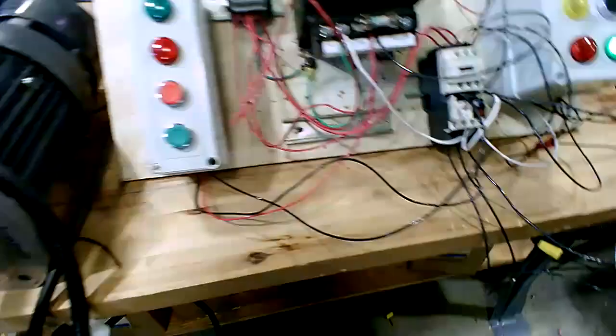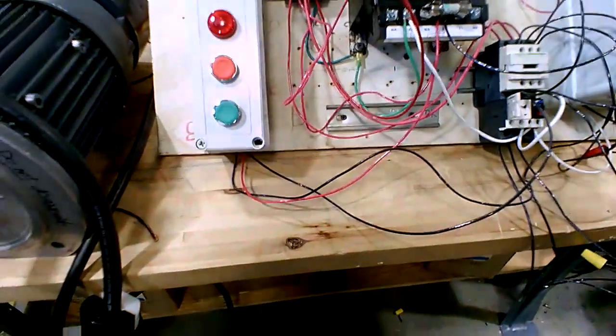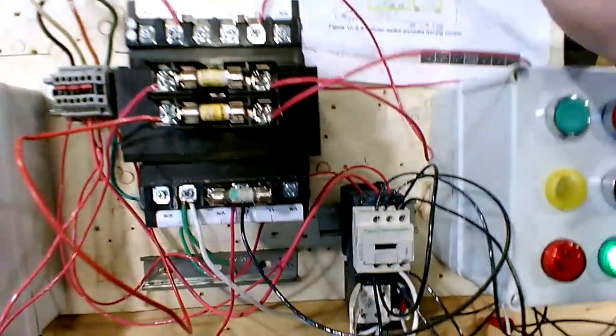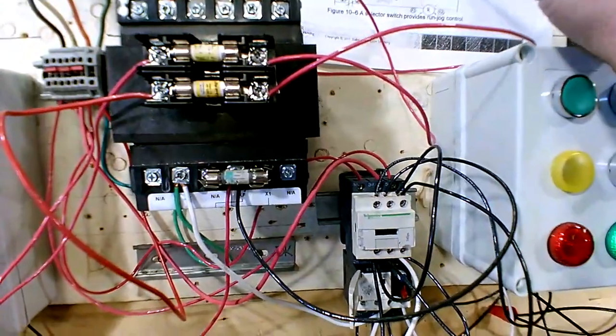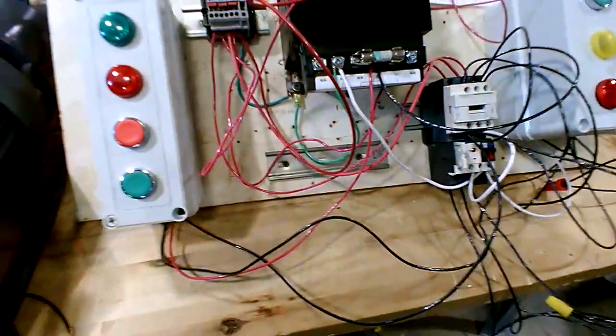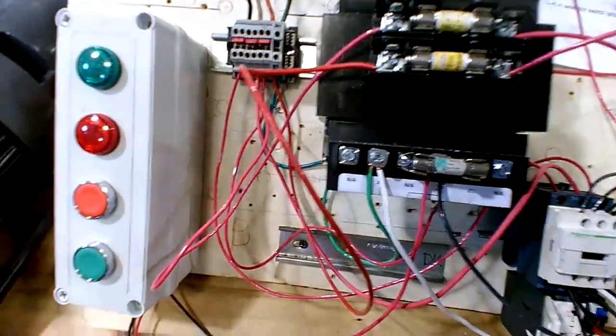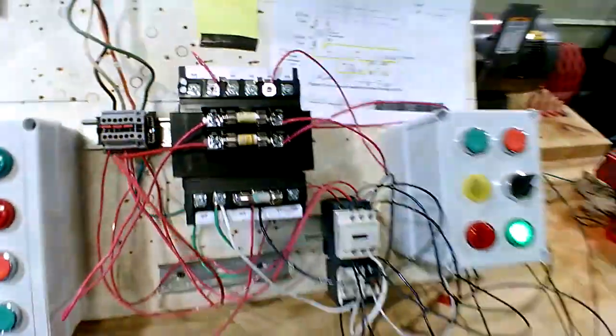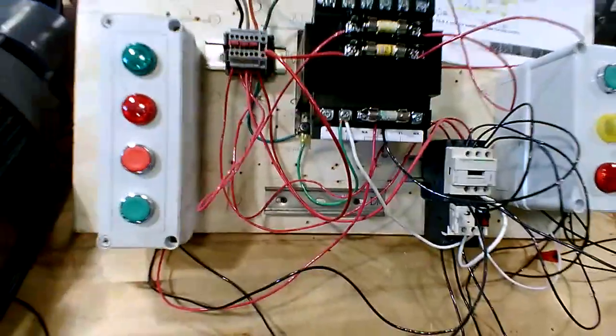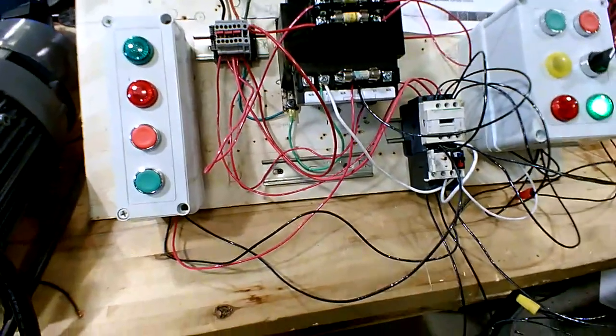So when the motor jams up for whatever reason, and it overloads the relay, overloads these heaters, those are going to cause that to pop open, and it's going to disengage. And when that opens up, it'll open these up and the holding contact will open up. So that's good there. If you put it in jog, go back to jog.